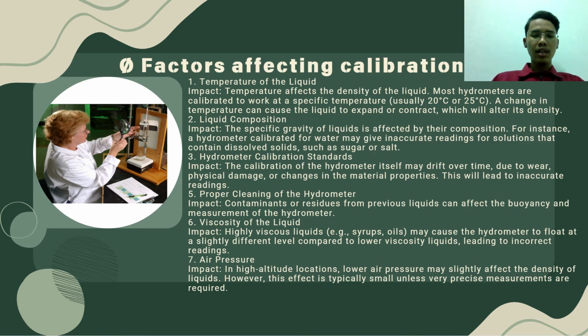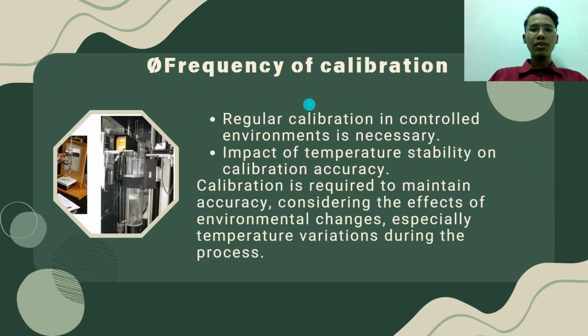Lastly is the air pressure. In high altitude locations, lower air pressure may slightly affect the density of liquid. However, this effect is typically small unless very precise measurements are required. Next slide is frequency of calibration. Regular calibration in a controlled environment is necessary. Secondly, impact of temperature stability on calibration accuracy. Calibration is required to maintain accuracy, considering the effect of environmental changes, especially temperature variation during the process. Next slide.